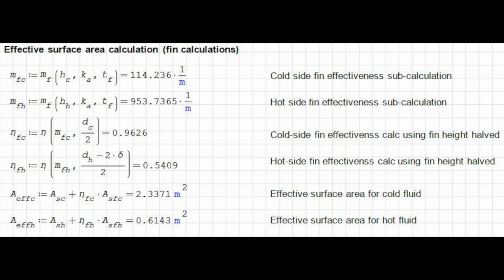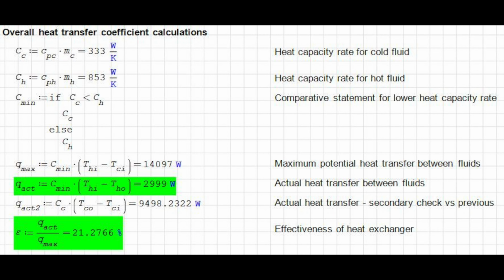So then we have the actual effective area, which is your surface area of the plate plus the correction factor multiplied by the total surface area of the fins, and that gives you your total effective surface area for that fluid. So we have the cold and the hot fluids here. Next, we have the comparator for the cold fluid heat capacity rate versus the hot heat capacity rate. So the cold fluid here is 333 watts per Kelvin, and the hot fluid is 853. This is what I was talking about when I said one is the limiting factor over the other. Well, you need almost 3 times the amount of the cold fluid here, so 3 times the amount of airflow, in order to match this modest water flow that we have going on here.